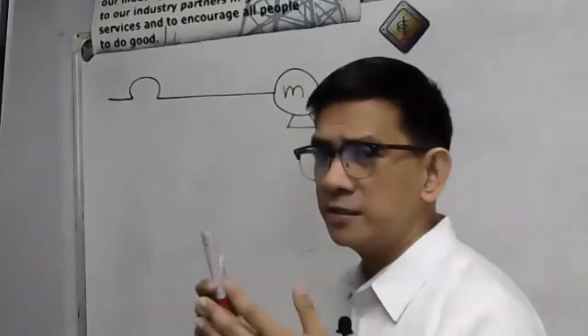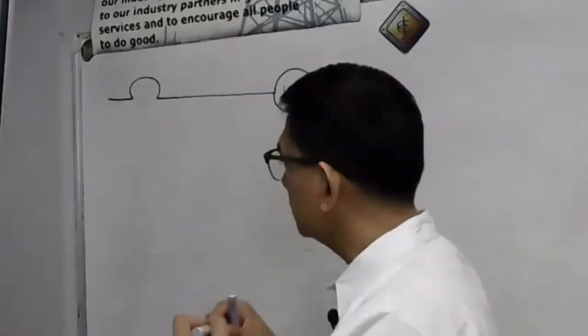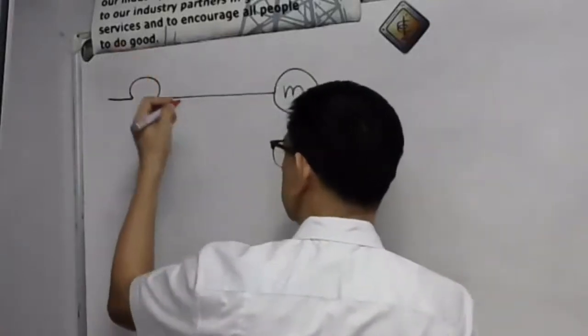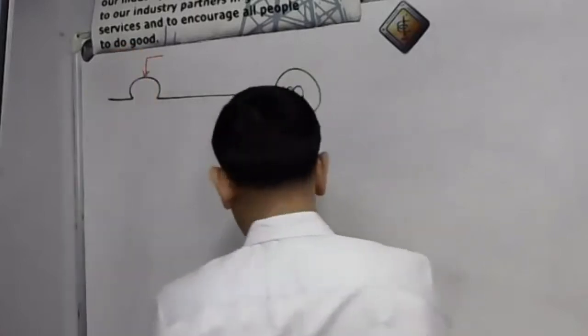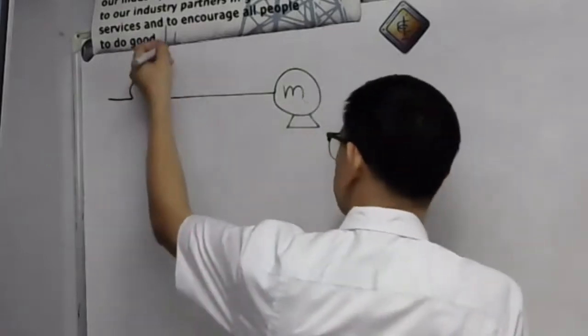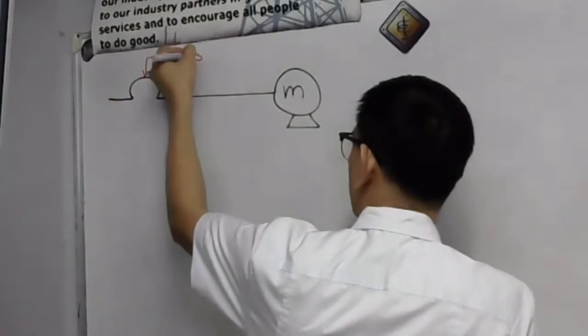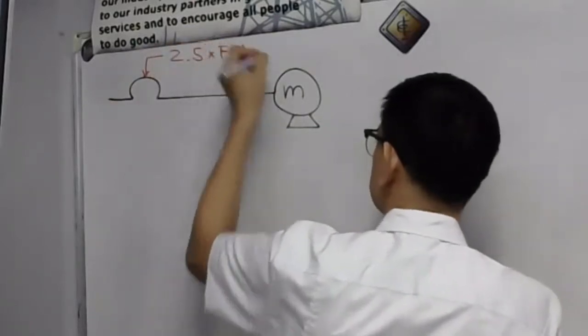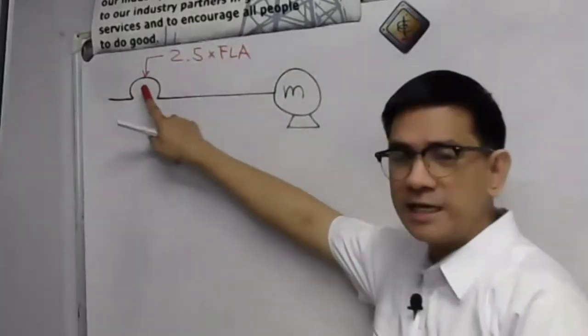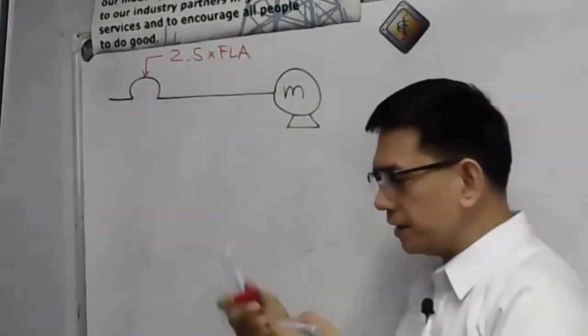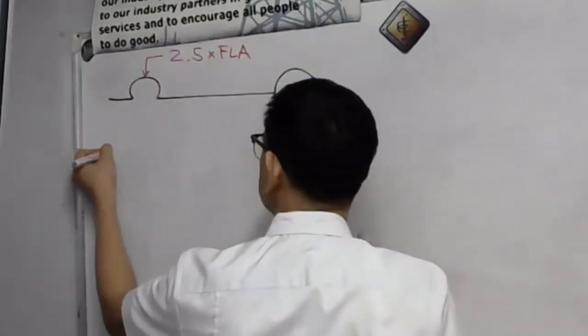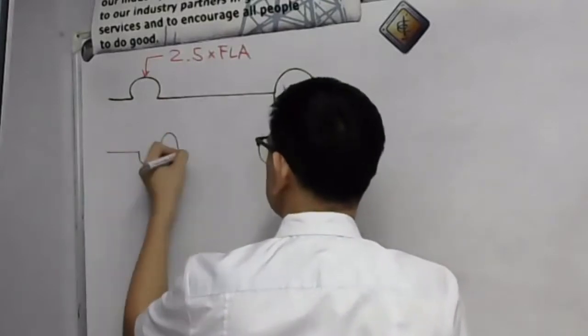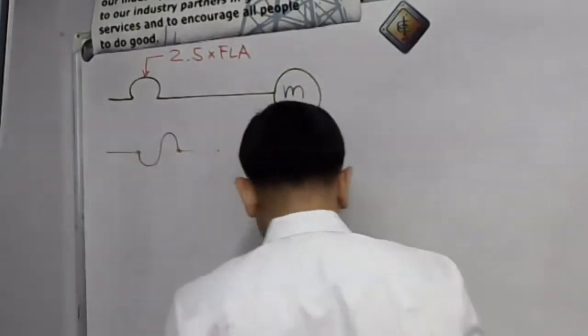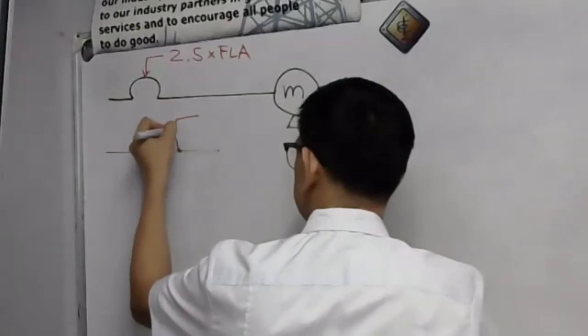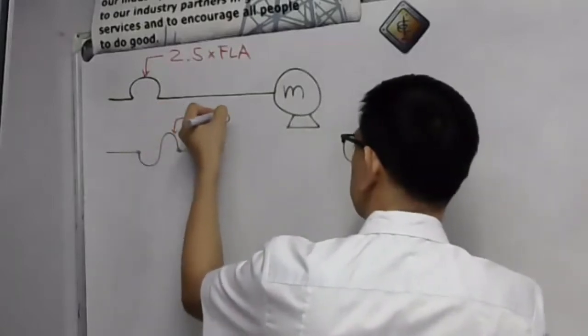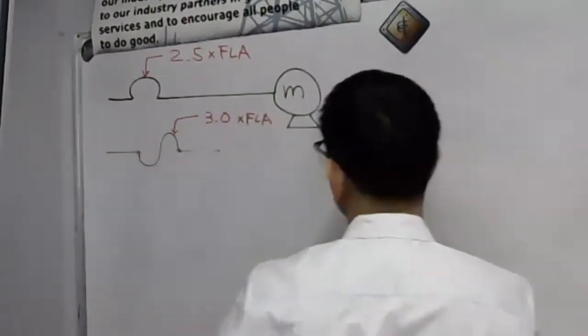So, we are talking here of a licensure exam. Board exam pinag-uusapan natin dito. In the board exam, if we are sizing a circuit breaker, our multiplier is 2.5 multiplied by the full load amperes. That is the maximum size of the circuit breaker. But if you are sizing a fuse, the size is 3 multiplied by the full load amperes.